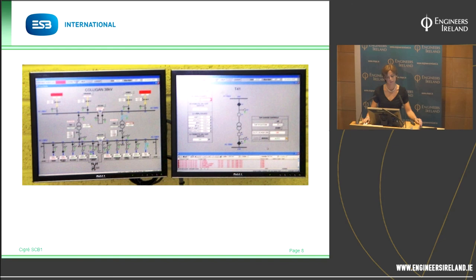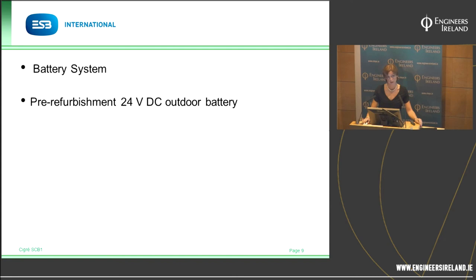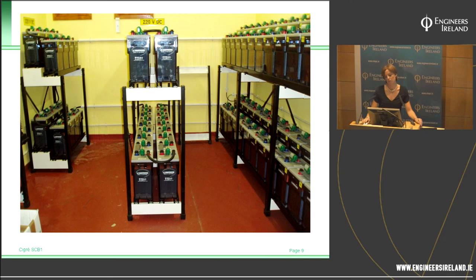The battery system: those old 38 kV stations would have had a single outdoor 24-volt DC battery. When we started with the pilot, when we were doing indoor GIS stations, we set up a battery something like that. We were using lead acid wet cell batteries. They vent off gases during their charging cycle, so they need to be kept in their own room. And there's also always a small risk of acid spillage. But obviously that wasn't going to be suitable for a module.